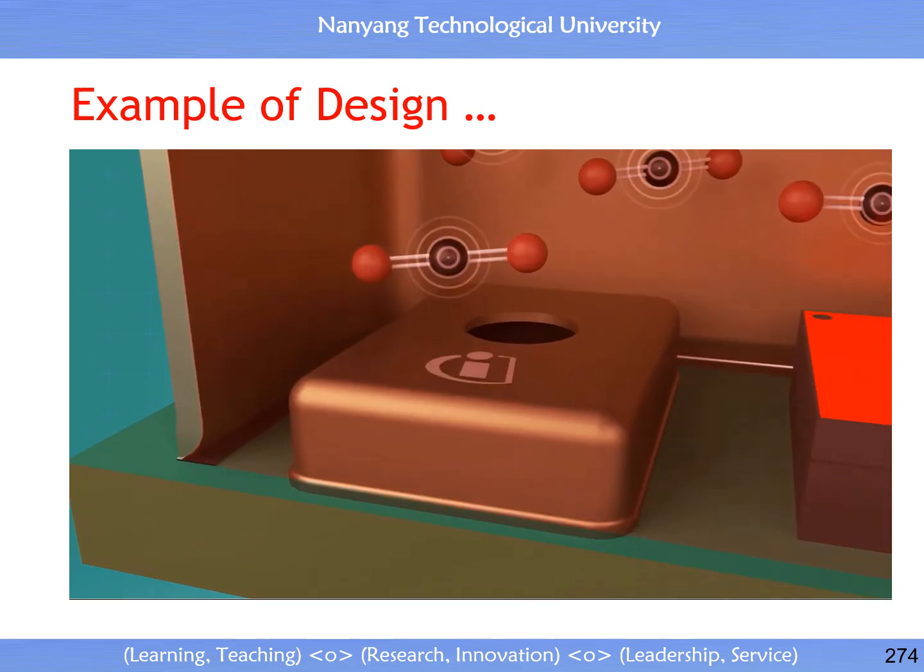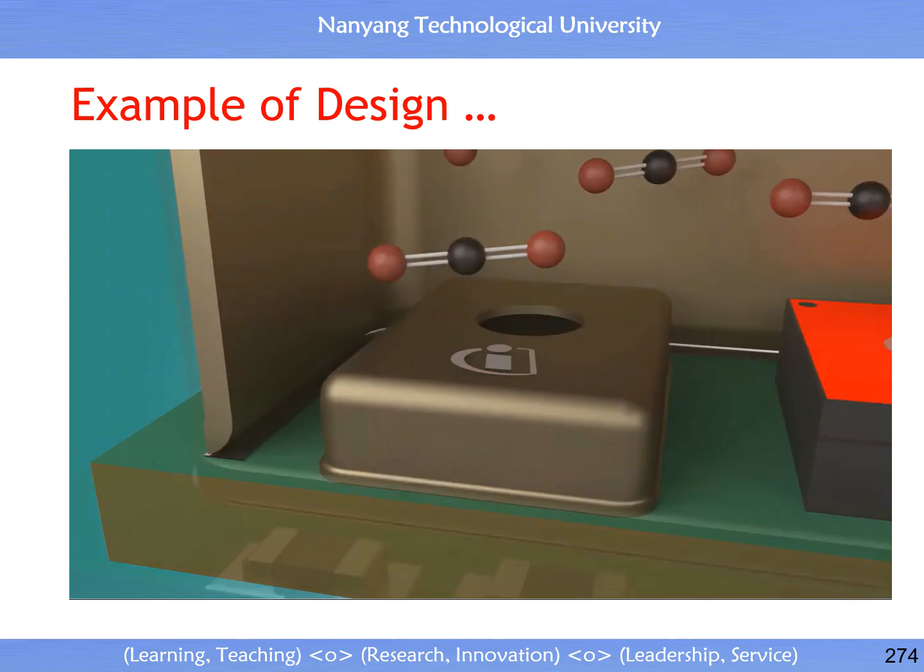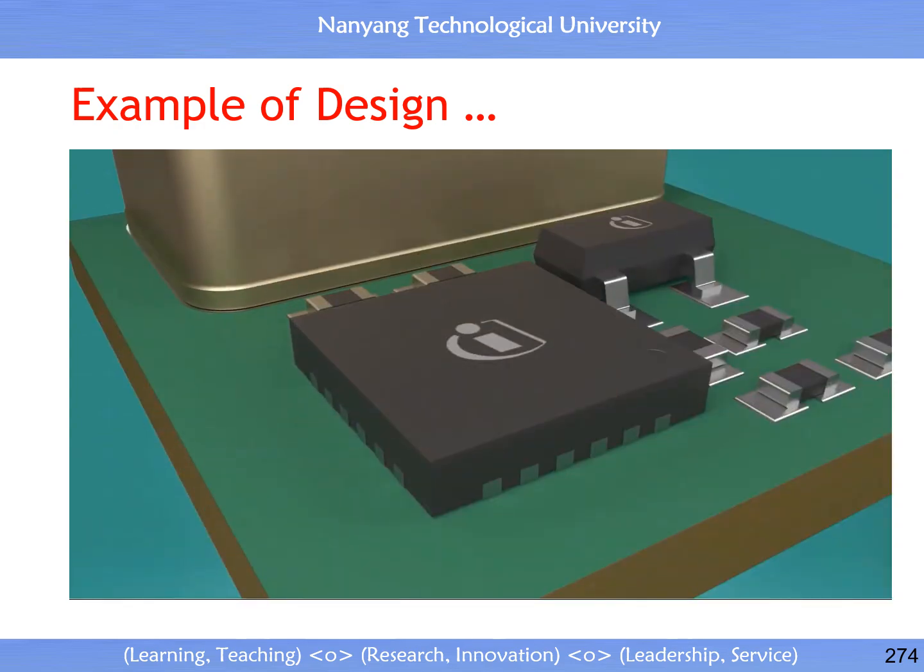An Infineon XENSIV MEMS microphone with an exceptionally high signal-to-noise ratio is placed inside the absorption chamber and detects these very small changes in pressure. An integrated microcontroller converts the MEMS microphone output into a CO2 concentration reading.